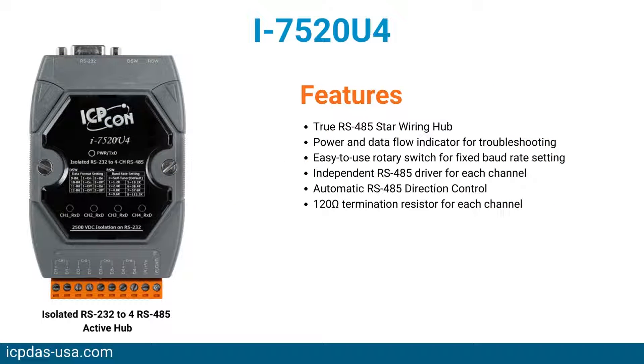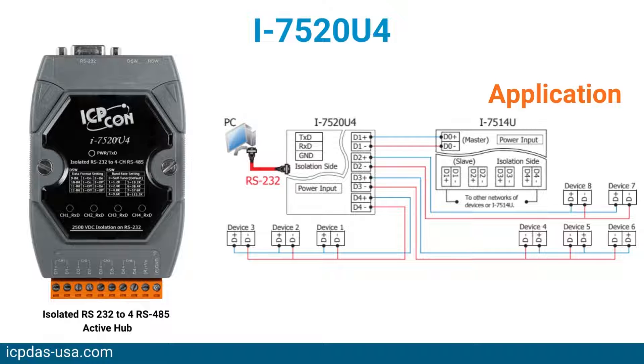The I-7520U4 is an isolated RS-232 to 4-channel RS-485 active star wiring hub. It has four independent RS-485 output channels and one RS-232 input channel. Each output channel is equipped with an individual driver, and data from a master to the input channel will simultaneously be forwarded to all four output channels.